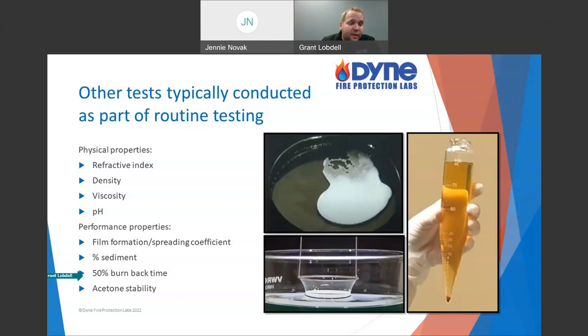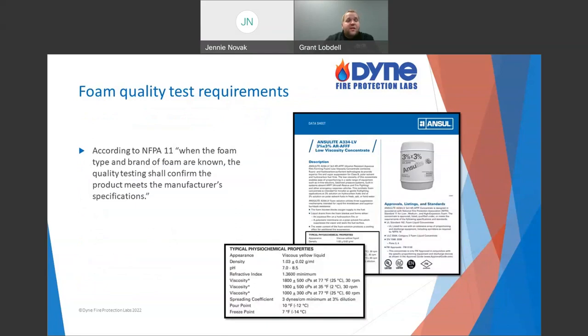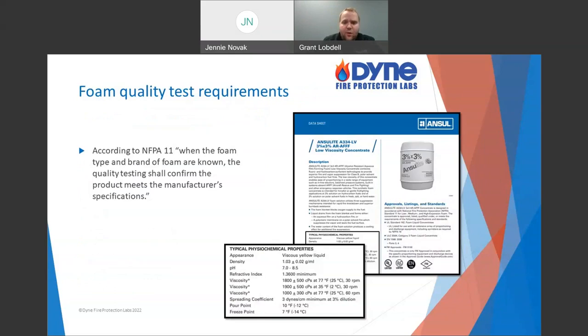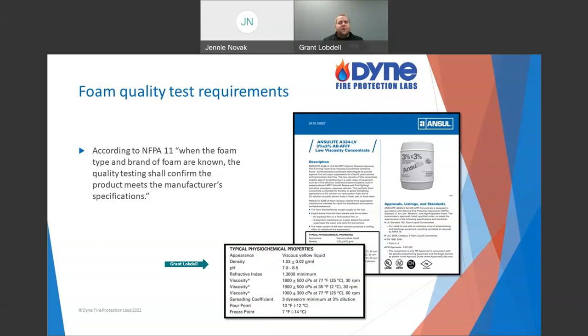Those are the tests you might see conducted — a brief overview. Once we get these results, what do they mean? What are the requirements? NFPA says that when a foam type or brand is known, you should compare results to the manufacturer's specifications. On screen is an example — an ANSUL data sheet for their 3x3 low-viscosity alcohol-resistant AFFF product — showing typical properties you can expect. We compare results to that when the product or brand is known.